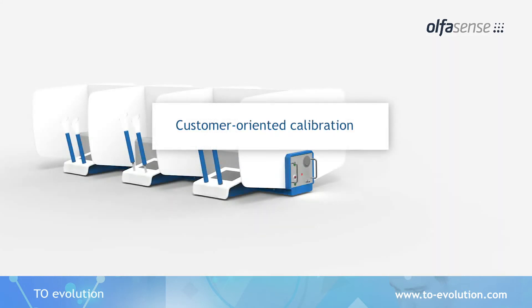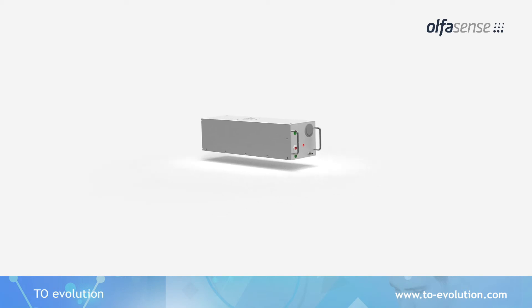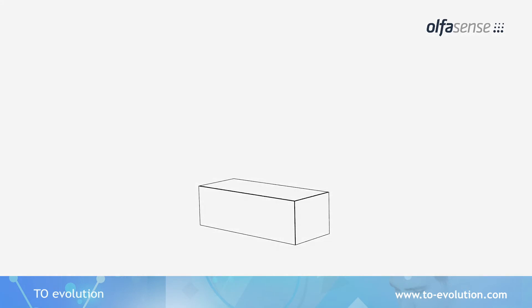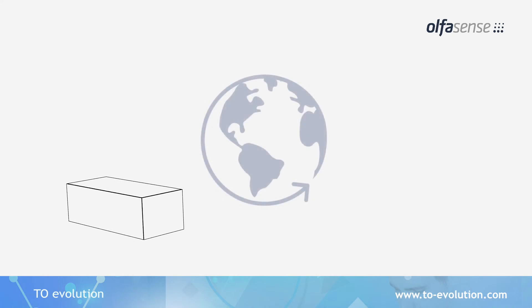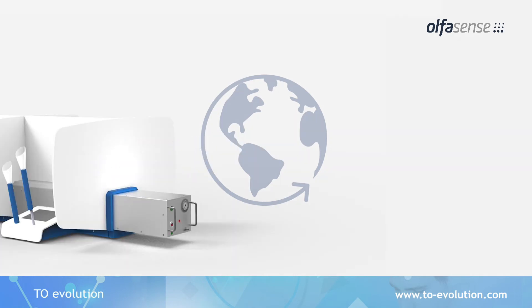Whenever a calibration or maintenance in accordance with ISO 17025 is required, the dilution unit can be easily and quickly removed from the support bar for transport. A specially provided transport box ensures safe shipment to the Olfasense calibration laboratory. This also saves costs incurred for visits of a technician during an on-site calibration.